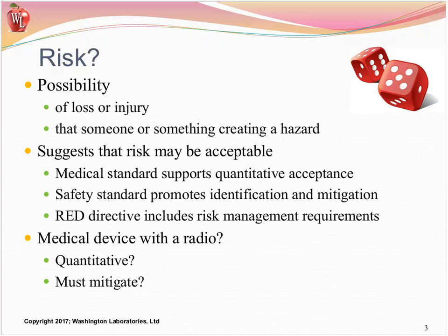So the radio systems, the wireless sensors, the wireless whatever, is a true element throughout. And we see this in our world of medical devices today, where especially those sensitive signals like an EKG, etc., use the wireless device to avoid the cable coupling from a radio. The wires can pick up medium frequency emissions and overpower the low-level signals, these little sensors that go on our body. So they're being replaced with RFID kind of things, where the medical device interrogates and gets a reply with a digital type signal, and the cable coupling from some of the other radios tends to take that away.